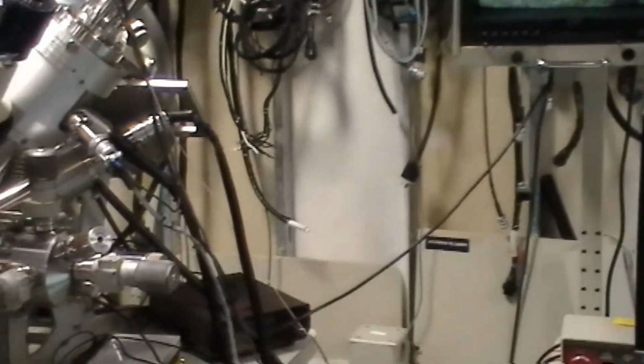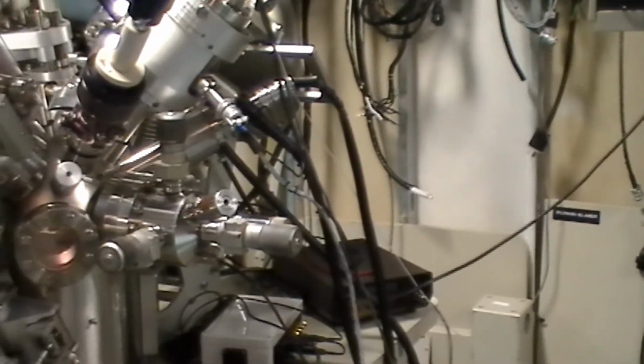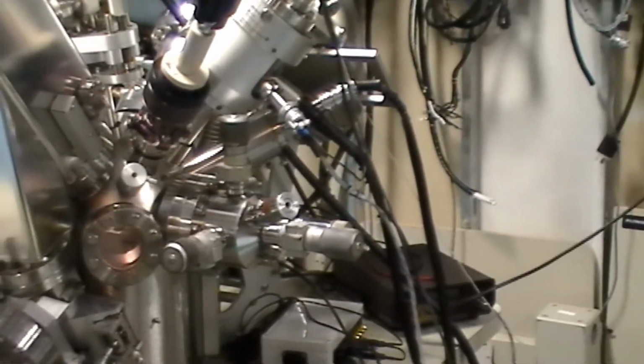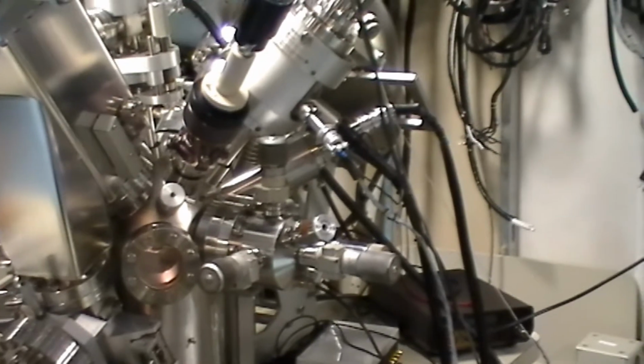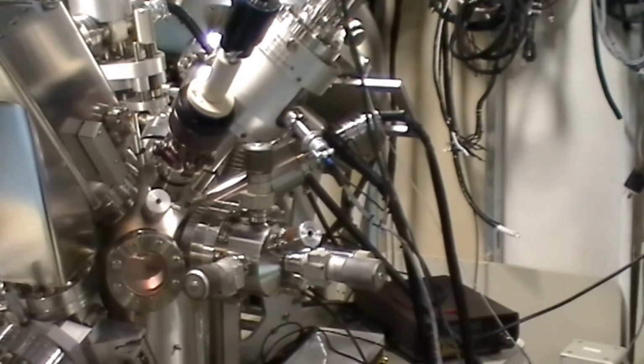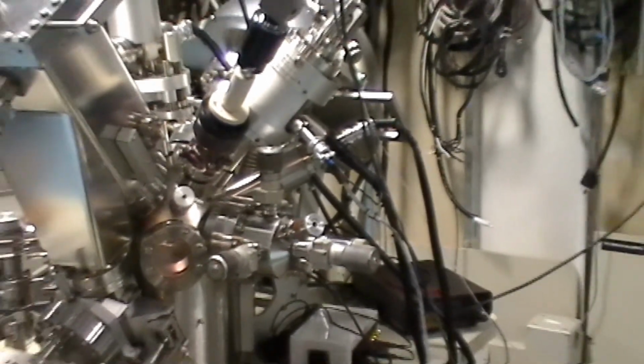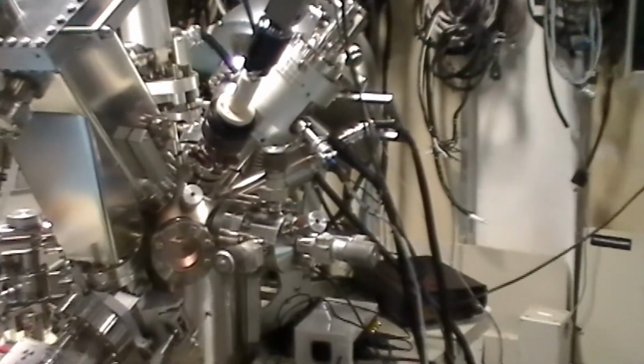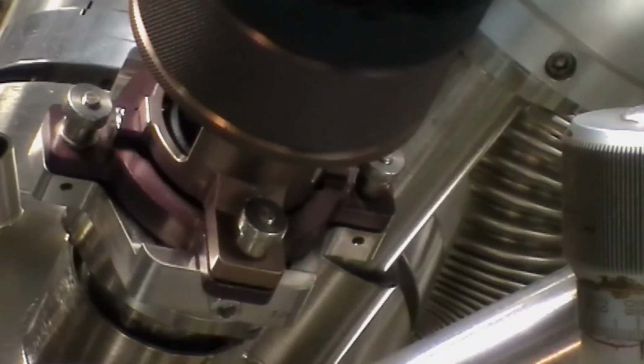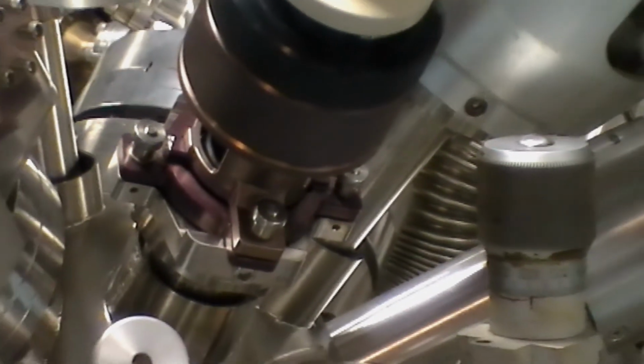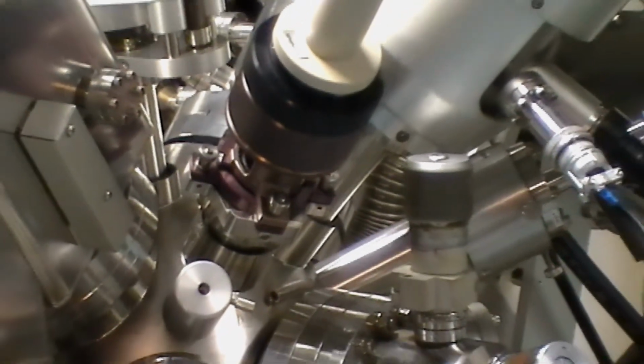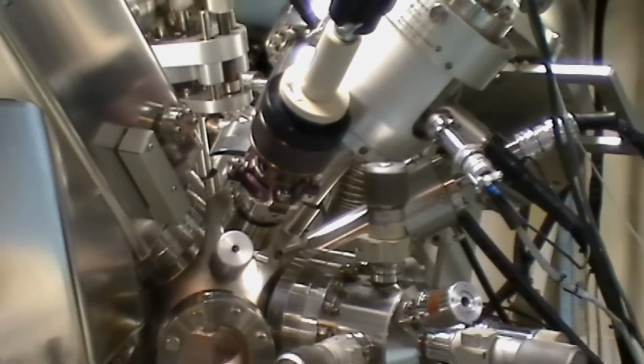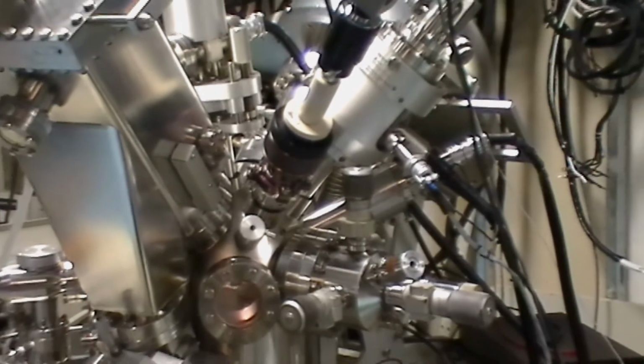Okay, so this is what the TV monitor and image and the software looking at the peak, and there's the specimen stage, and here's the camera. The focus ring on the camera is located at the base of the collar, and the X and Y are two little thumb screws that you adjust. Two axes for thumb screws, X and Y. So you can tilt the camera and get it to point where you want it to. You loosen the focus ring and you can adjust the camera in and out as necessary to get it to be focused.